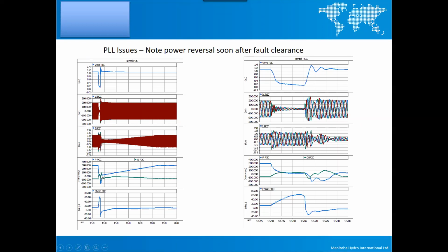If you look carefully, just after the fault was cleared, there's a power reversal. You were operating at 300 megawatts, but before it recovered, the power reversed to about negative 200 megawatts. This could have tripped certain elements, and the wind farm may not have stayed connected. This happens because that angle was not properly estimated by the PLL during this transient period. And again, it all boils down to that simple equation: power is equal to V1 V2 over X sine delta. I'm pretty sure you have studied that equation, the power flow across a transmission element inductor. That delta was not estimated properly. The VSC, voltage source converter, did not do the right job.